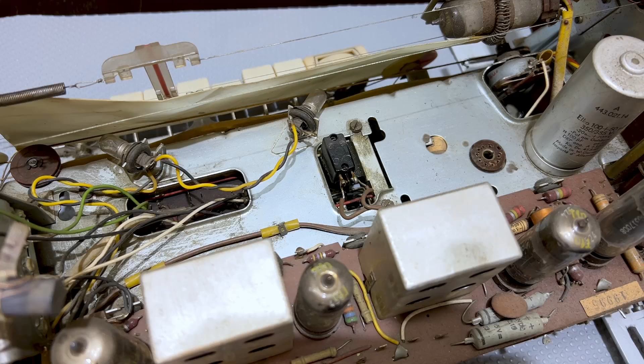So I'm going to give it a good blast of contact cleaner. Usually the contact cleaner gets into the switch, and we should be able to sort that out. Let's just check what we do get. We should get 65 ohms or so on the highest winding, and the one we've wired up is actually 60, well, it's jumping around because again... 58 ohms on the 220 volt winding.